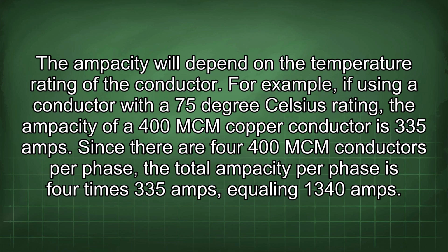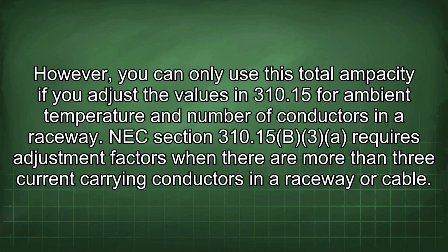Since there are 4 parallel 400 kcmil conductors per phase, the total ampacity per phase is 4 times 335 amps, equaling 1340 amps. However, you can only use this total ampacity if you adjust the values in 310.15 for ambient temperature and number of conductors in a raceway.